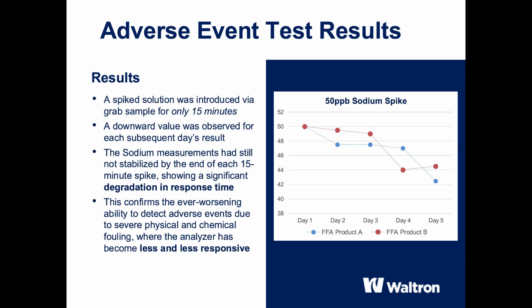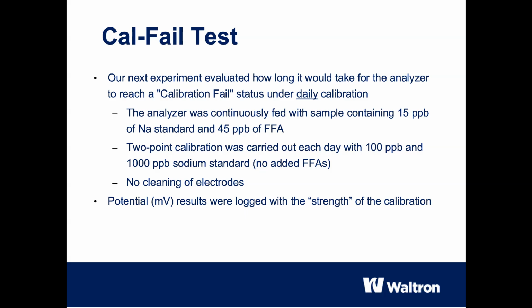On day 1, we still see a clear response close to the actual value of 50 ppb. However, by day 5, the measured peak value for product A has dropped below 43 ppb. This means that the progressive contamination from the FFA film acts like a mask, increasingly blinding the sensor. The device not only becomes inaccurate, it loses the ability to fulfill its core function, providing timely warning of a breakthrough.